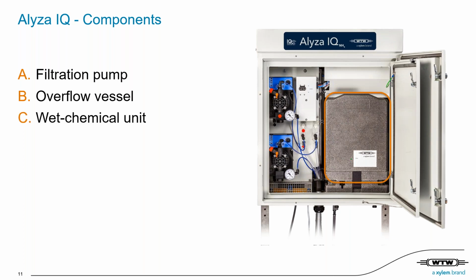This big part is the wet chemical unit. It is insulated and has a constant inner temperature of 20 degrees Celsius. So performance and reagent lifetime is optimized. The wet chemical unit itself is equipped with a status LED. You can directly see if a process is in progress, the maintenance mode is switched on, the wet chemical unit can be opened, or an error occurred. So maximum transparency for your analyzer. Now let's see what's inside of the wet chemical unit.